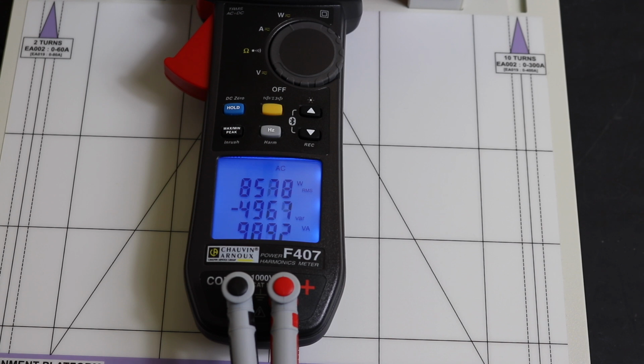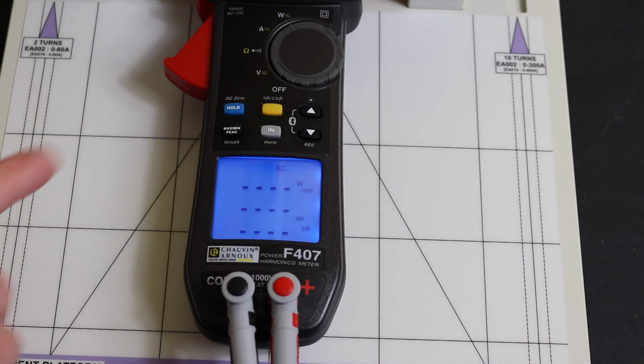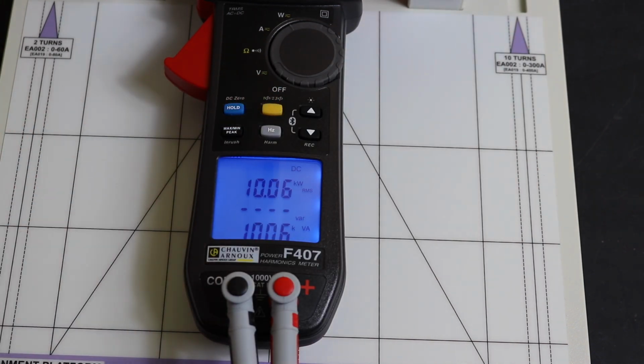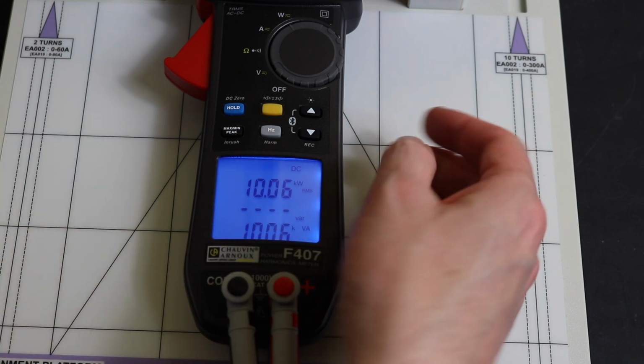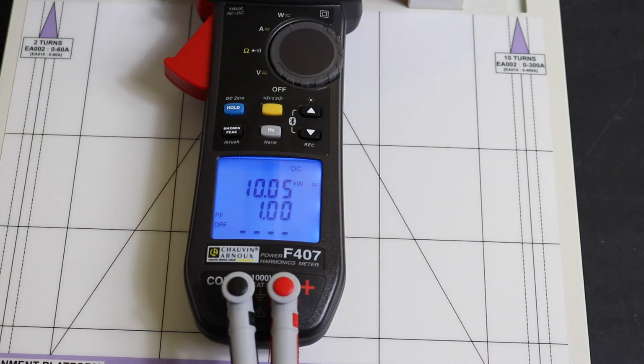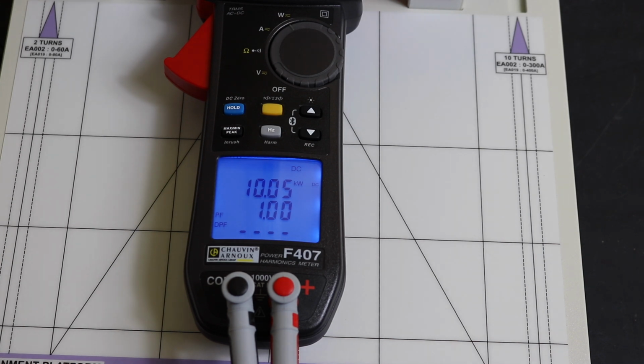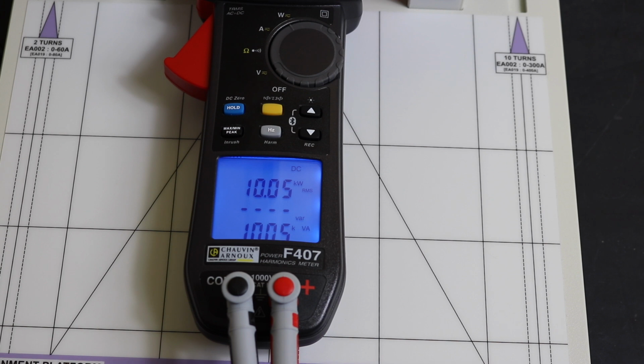We can also do this with DC as well, which is exactly the same. We change our yellow button here to select DC power, and then we've got our 10 kilowatts there, kVA matching the same. Not sure why we have power factor on our DC there. Don't know it's there, but doesn't really mean an awful lot with that one. I can't change the phase angle on DC anyway. But that's our power factor. That's the power measurements that are available on the instrument.